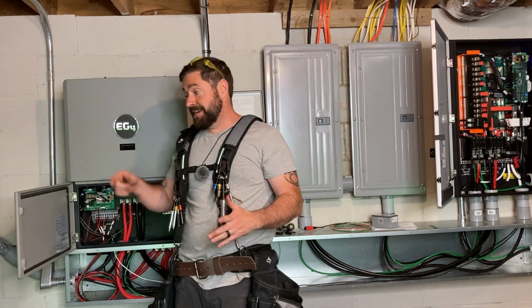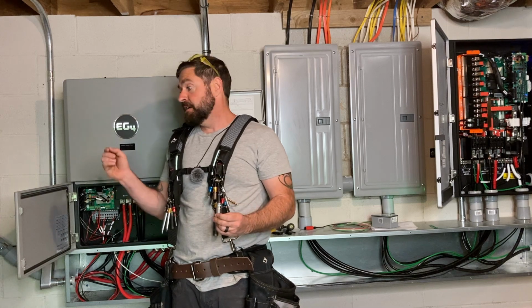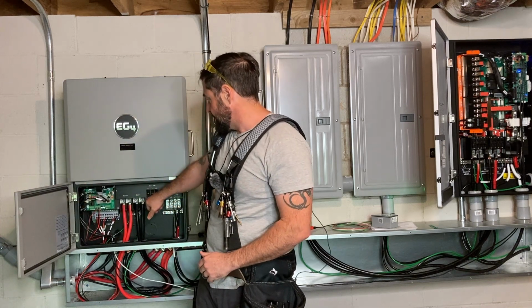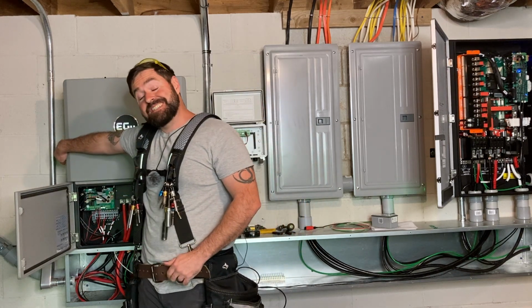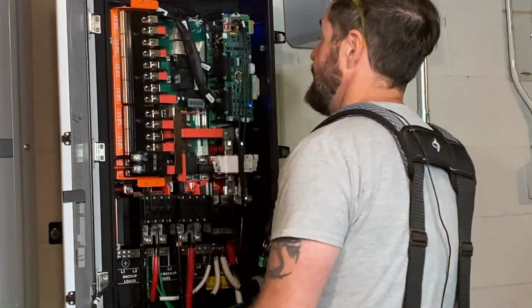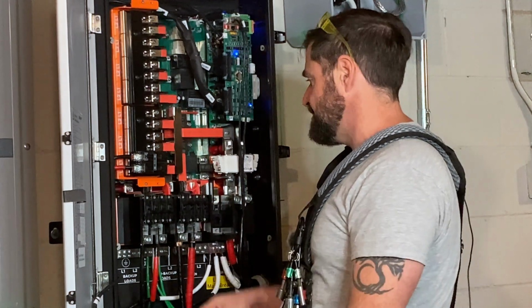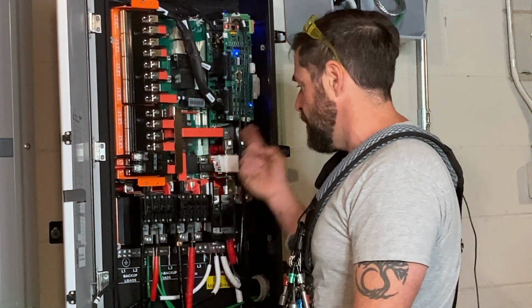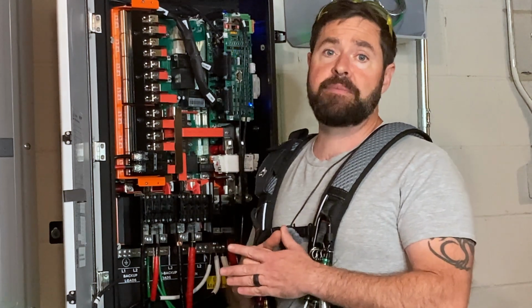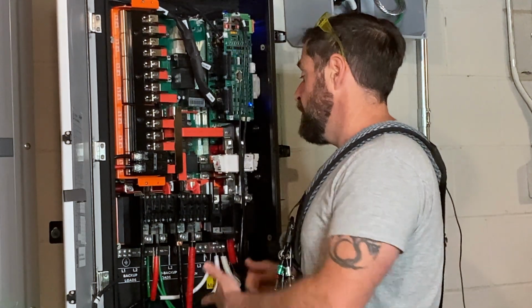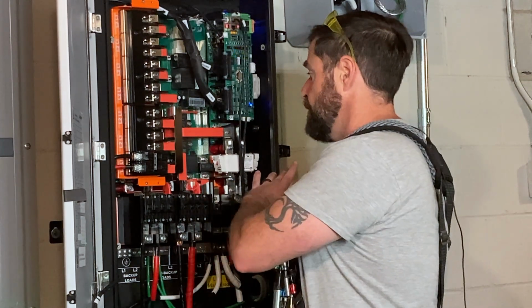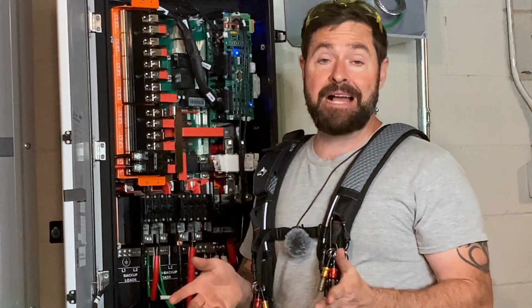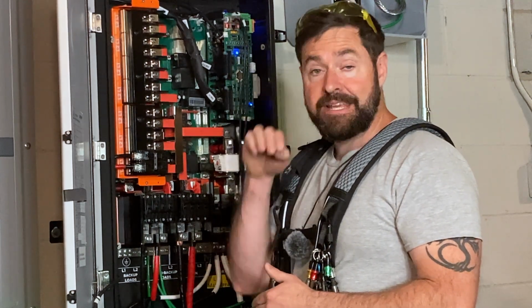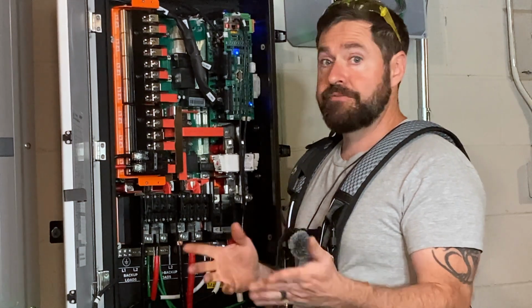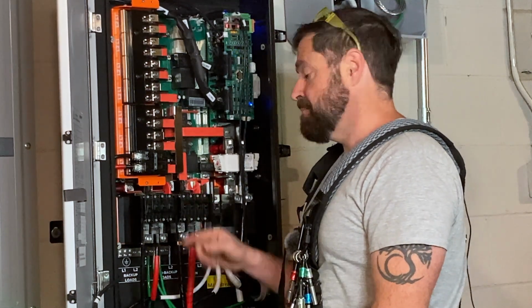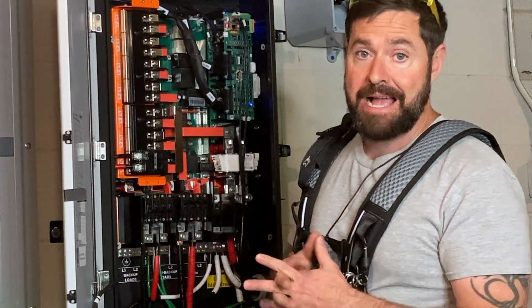Alright, so I've got my battery switches off, battery circuit breakers off, battery disconnect off, DC disconnect off for the solar panels, and the FlexBoss breaker off in the GridBoss. I turned off my backup loads breaker and turned on the grid bypass. That did in fact allow me to pass utility power through the entire GridBoss to both my non-backed up and backed up panels. So in the event you get a rapid shutdown event, or you've turned a bunch of stuff off, using that grid bypass is an easy way to get power to your backed up loads.